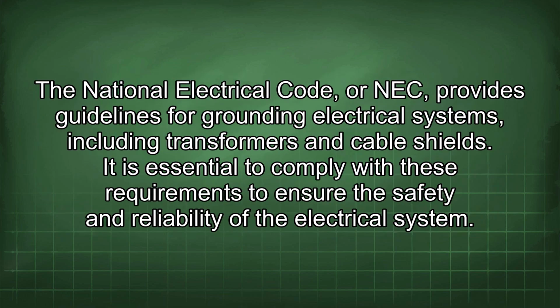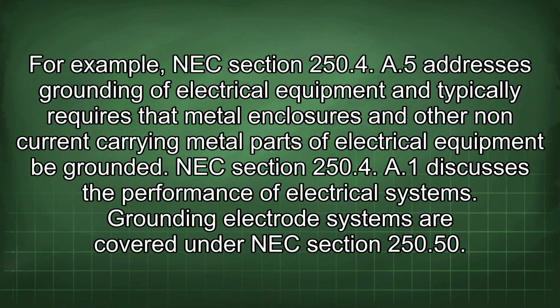The National Electrical Code, or NEC, provides guidelines for grounding electrical systems, including transformers and cable shields. It is essential to comply with these requirements to ensure the safety and reliability of the electrical system. For example, NEC Section 250.4(A)(5) addresses grounding of electrical equipment and typically requires that metal enclosures and other non-current-carrying metal parts of electrical equipment be grounded. NEC Section 250.4(A)(1) discusses the performance of electrical systems. Grounding electrode systems are covered under NEC section 250.50.